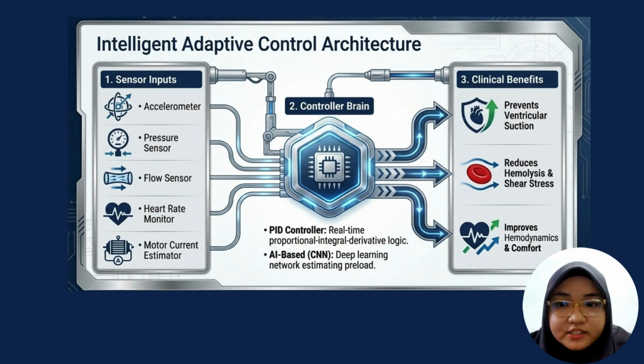The adaptive system operates using a closed-loop control mechanism. So, there are several physiological sensors integrated into the LVAD system, including the accelerometer, pressure sensor, flow sensor, heart rate monitoring, and Hall effect sensor for rotor position monitoring. In addition, the system can also implement a sensorless estimation method using motor current and pump flow signal to estimate the preload condition without requiring an invasive pressure sensor.